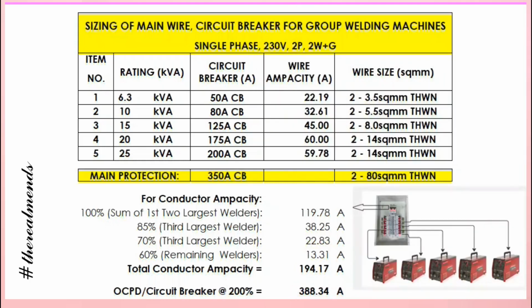We're almost done with our short discussion. To sum up, our output for the main wire and circuit breaker is a 350 ampere circuit breaker and two sets of 80 square mm THWN. This is what we will install for our protection: the wire and its circuit breaker.